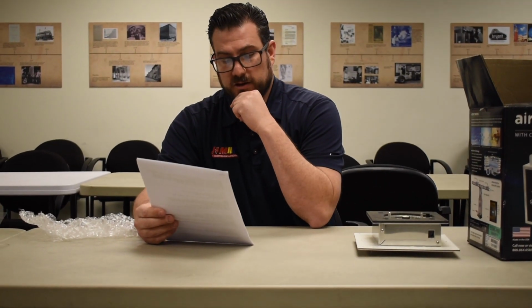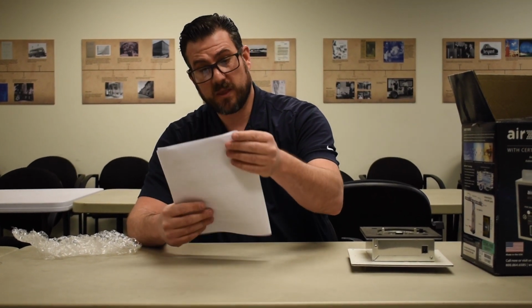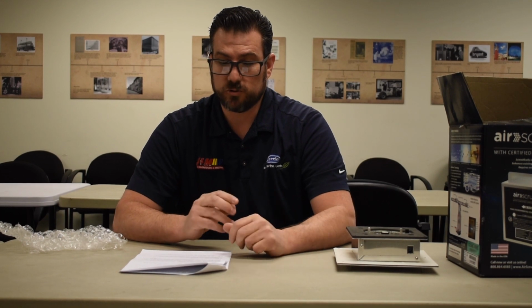This is from a website called explainthatstuff.com, and we'll provide a link for that. In a nutshell, this is paraphrased: ultraviolet light shines onto the catalyst, which converts water in the air into hydroxyl radicals, which are highly reactive, short-lived, uncharged forms of hydroxide ions. So we've got that word ions again. Those small, agile hydroxyl radicals then attack bigger organic carbon-based pollutant molecules, breaking apart their chemical bonds and turning them into harmless substances such as carbon dioxide and water.